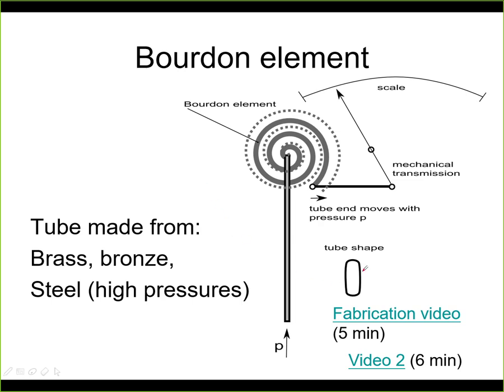The Bourdon element is a tube that typically has this shape, like this. This is the cross section. So it is a tube that is flat, and then the tube is bent in a spiral. So it typically looks like this. It does not need to be an entire spiral like this. It can be just a semi-arc, for example. This Bourdon element is closed at one end.